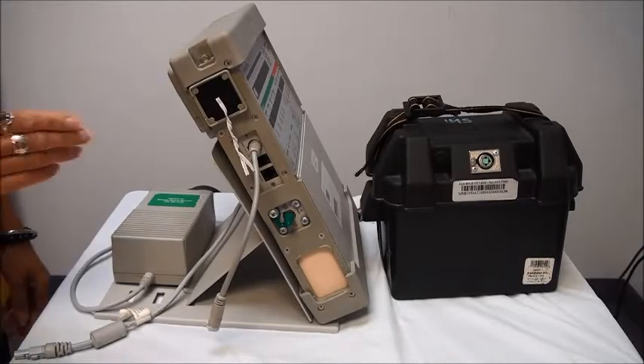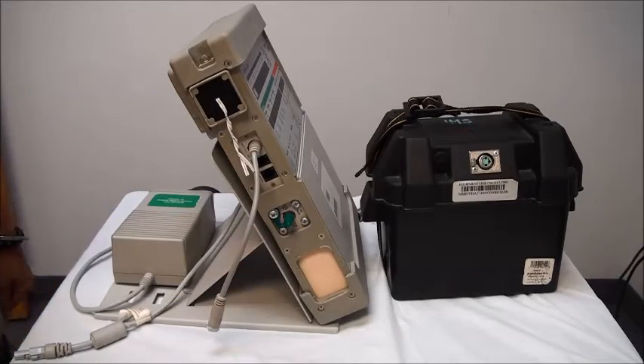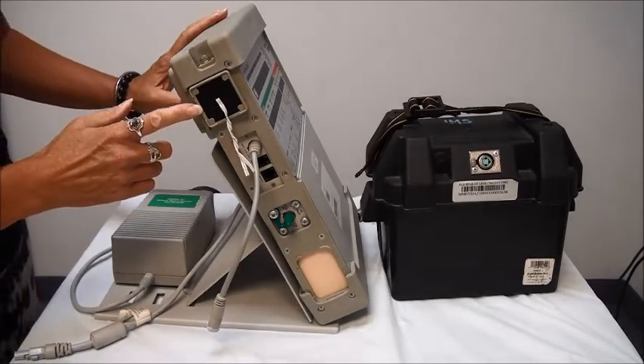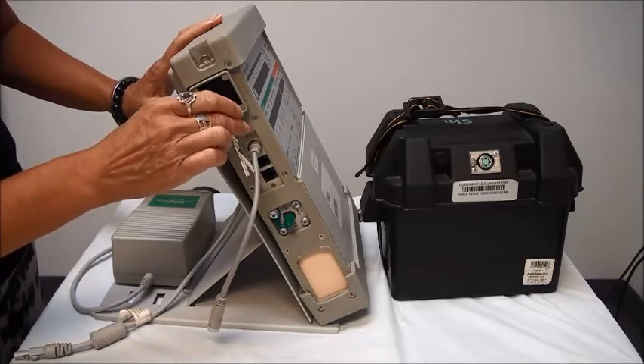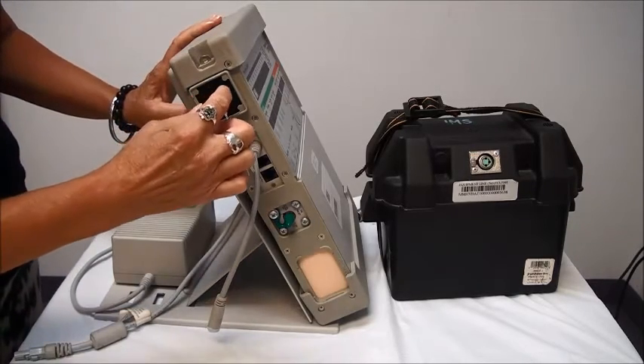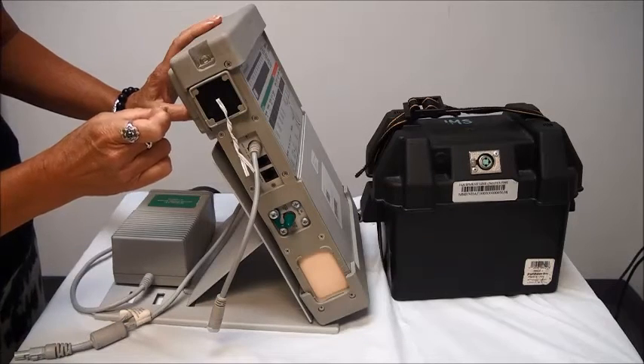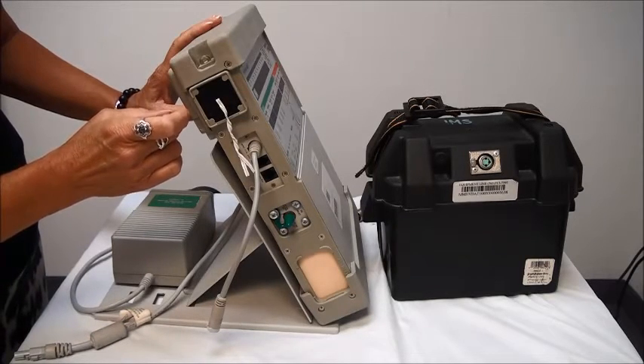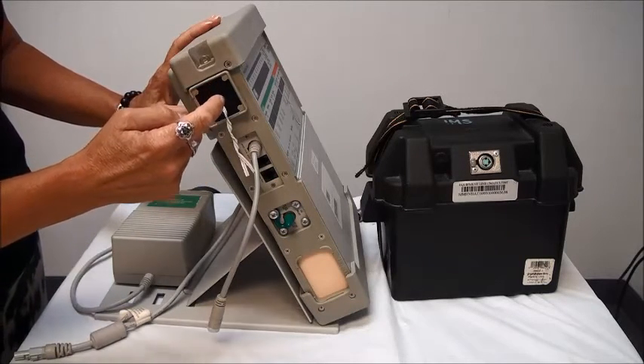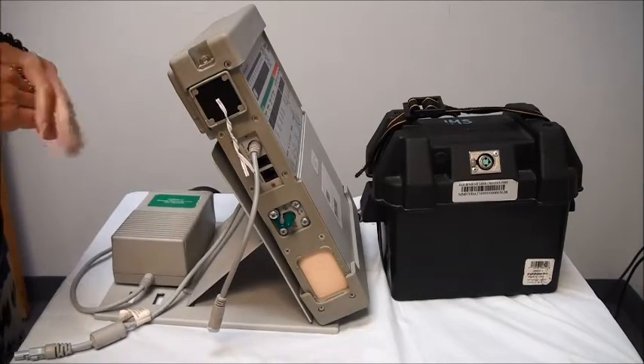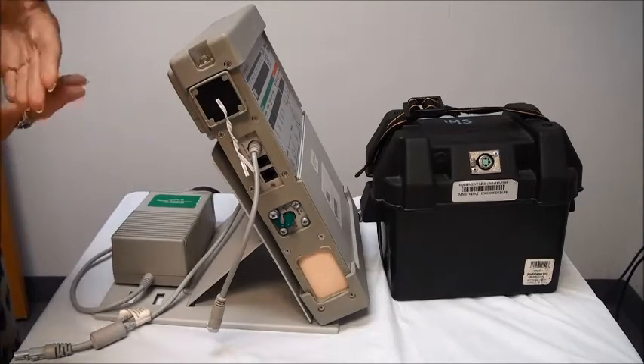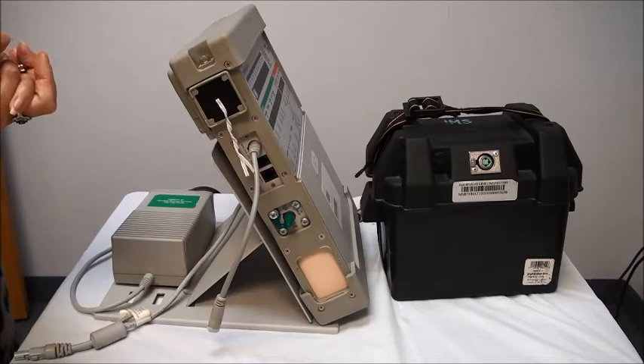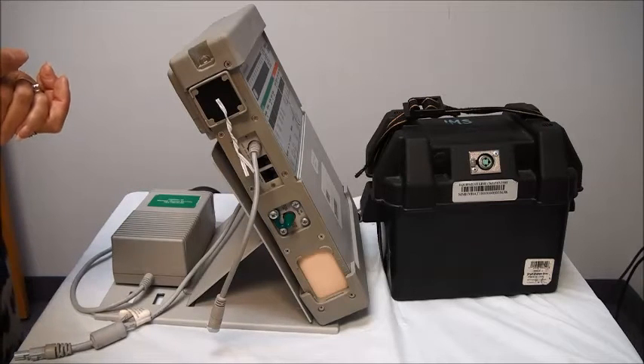Okay, first we're going to look at the right side of the ventilator. On the top of the ventilator you have a filter. You need to take care when you're taking the filter cover off to change or clean your filter that you're not taking anything and poking inside the filter. There's a fan behind the filter, and if you poke into that fan, you're going to cause problems with your ventilator.